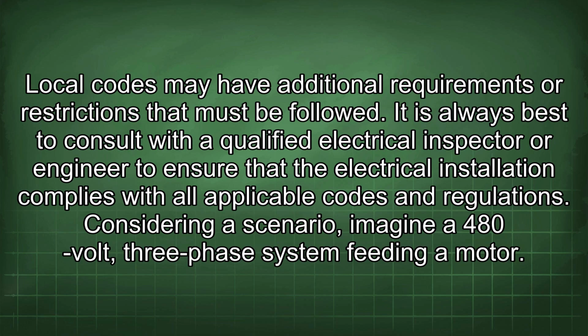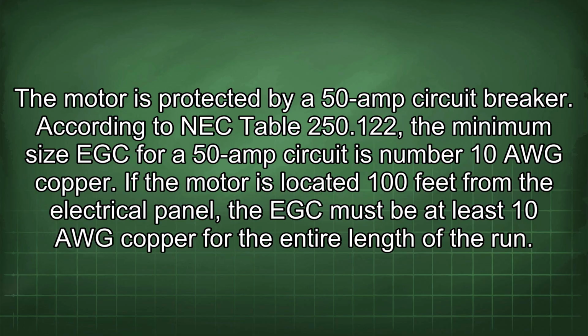Considering a scenario, imagine a 480-volt, three-phase system feeding a motor. The motor is protected by a 50-amp circuit breaker. According to NEC Table 250.122, the minimum size EGC for a 50-amp circuit is number 10 AWG copper. If the motor is located 100 feet from the electrical panel, the EGC must be at least 10 AWG copper for the entire length of the run.